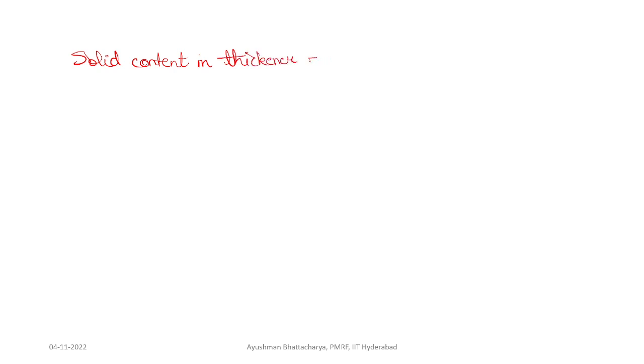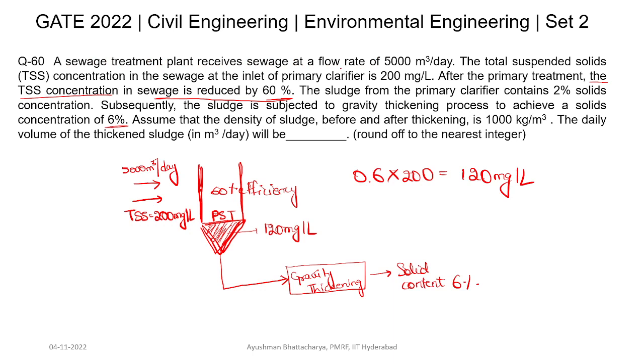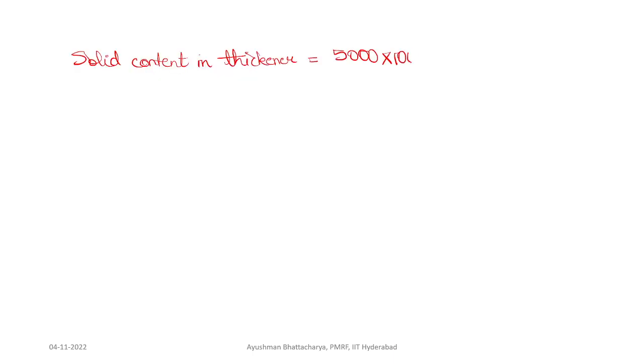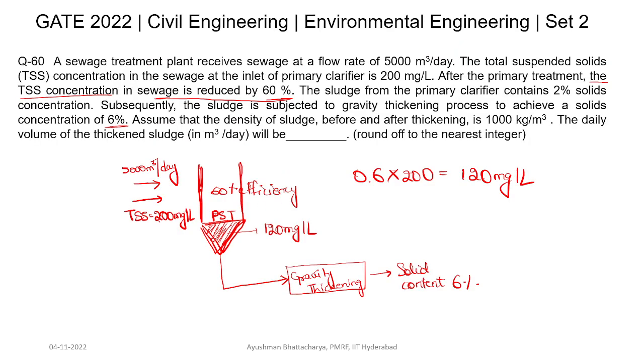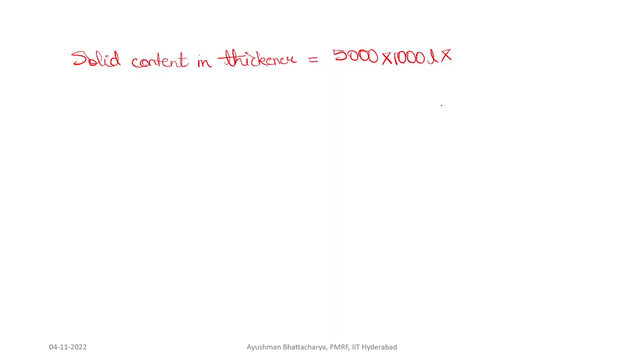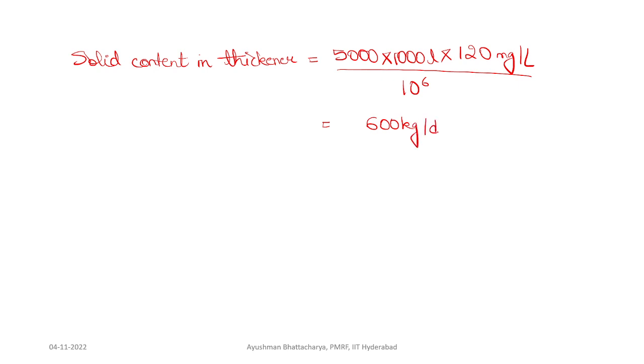The sludge solid content going to the gravity thickener equals total flow rate 5000 m³ per day. Converting to liters: 1 m³ = 1000 liters. So 5000 × 1000 liters × 120 mg per liter of solid. To convert mg to kg, divide by 10⁶. This gives 600 kg per day — which is the solid content going to the gravity thickening process.